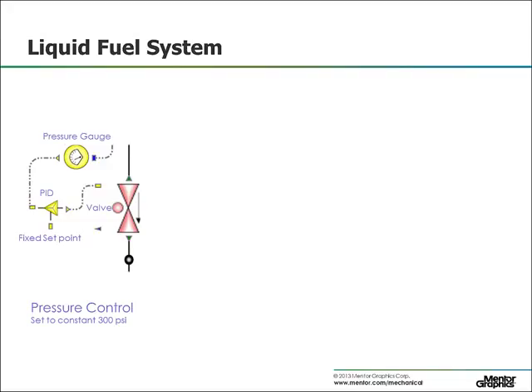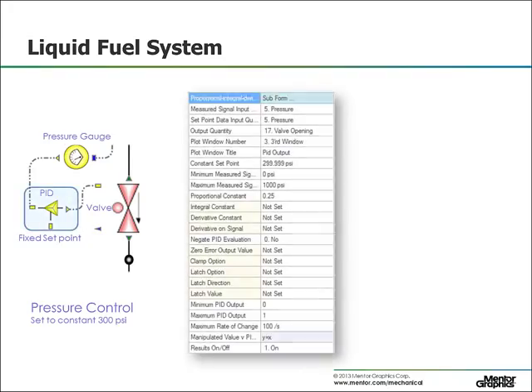Next, we'll look at how the pressure control system operates. Similar to the flow control system, we use a gauge to measure pump output pressure and feed that to a PID controller. Here, we keep a constant 300 psi set point, so we do not need to use the optional variable set point signal input of the controller seen here. The PID controller opens a valve that bypasses flow back to the inlet of the pump to regulate the output pressure.